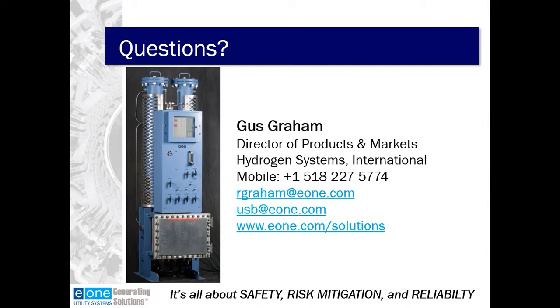Okay, and there was a follow-up to that last question. There were some clarification issues. So it's purging hydrogen out of the dryer, not regen. Oh, I'm sorry, purging hydrogen. Yep, no, that's good. So purging, 15, 20 minutes. We want to look for a minimum of two volume changes of gas flowing through the towers at that point in time. So depending on the regulator setup and the pressure you're delivering the gas at, you're looking at 30 minutes in that range to an hour max.